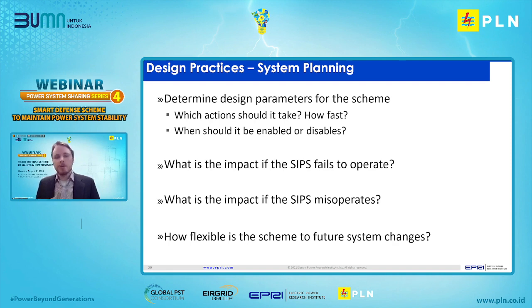It is also very important to consider what would happen if the defense scheme fails to operate, such as what happened in Norway and in Argentina. And also if the SPS scheme misoperates. So if it operates due to a failure of communications or human error or during maintenance, is the system resilient to all of these? And also, how flexible is the system to future system changes? So while the system is complex today, you may have more generators coming on in future. You may have more wind and solar PV farms. So is the scheme flexible so that it will still behave as expected for those future changes?